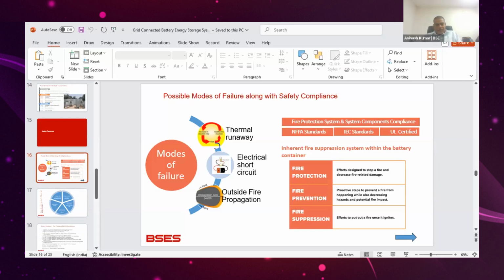And there are majorly 3 modes that could cause fire or failure: thermal runaway, electric faults, and so on. The guidelines available with this battery, we asked the developer to test as per the NFPA standard and give the test report as well as the certificate. IEC standards we have followed, UL standards we have followed, especially regarding fire safety.